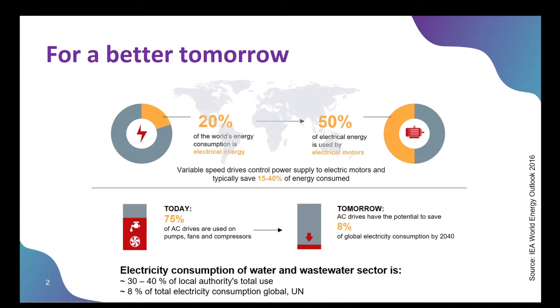But by adjusting the speed of the motor to the need of the application, we can typically save. And this is especially true in applications with quadratic torque characteristic like fans and pumps and compressors. So there is a very big opportunity of energy saving using variable speed drives. We can see that up to 8% of global electricity consumption can be saved by 2040 by using variable speed drives. And looking at the water and wastewater sector, we can see that between 30 and 40% of local authorities' total use of electric energy goes to this kind of application. And globally, 8% of the total electricity consumption is used by the water and wastewater sector.